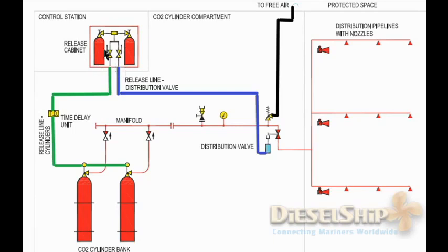The release cabinet has two pilot cylinders and is enclosed inside a cabinet with a door. Once the door is opened, it gives audible and visual alarms, and it may also trip ventilation fans and stop some fuel pumps — this varies by ship. But it must definitely give an audible and visual alarm and must stop the ventilation fans.